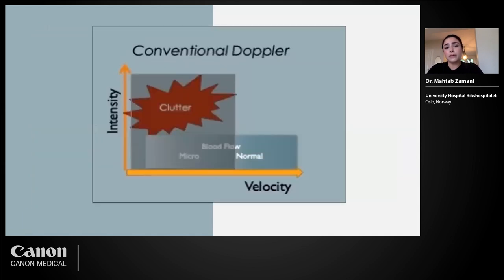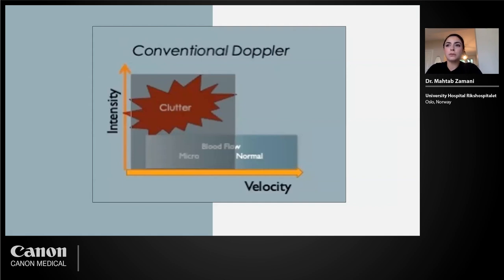These leaky neo-vessels are the main cause of intraplaque hemorrhage, and intraplaque neovascularization is therefore a strong indicator of future plaque destabilization and rupture. The vasa vasorum extensions into the full vessel wall thickness are small in size and have low-velocity blood flow — which is the fundamental problem with conventional Doppler imaging. Additionally, conventional Doppler applies a motion wall filter designed to remove artifact and clutter from nearby structures. However, in this process, it may also remove the micro-circulation.